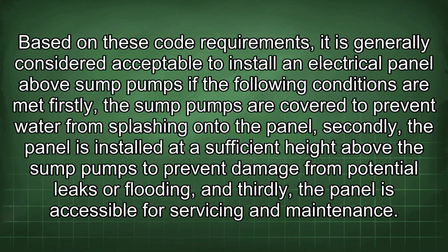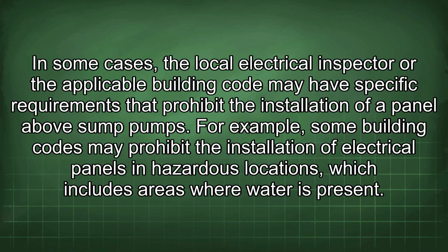Based on these code requirements, it is generally considered acceptable to install an electrical panel above sump pumps if the following conditions are met. Firstly, the sump pumps are covered to prevent water from splashing onto the panel. Secondly, the panel is installed at a sufficient height above the sump pumps to prevent damage from potential leaks or flooding. And thirdly, the panel is accessible for servicing and maintenance. In some cases, the local electrical inspector or the applicable building code may have specific requirements that prohibit the installation of a panel above sump pumps.